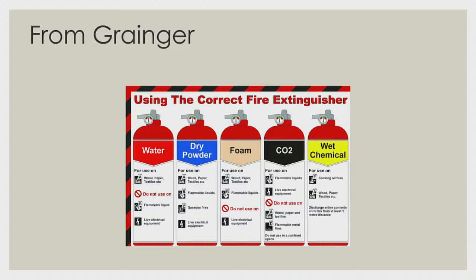Foam is good on wood, paper, textiles, flammable liquids, and not to be used on electrical equipment. CO2 is good for flammable liquids, live electrical equipment, but don't use it on wood, paper, textiles, flammable metal fires, and don't use it in a confined space.